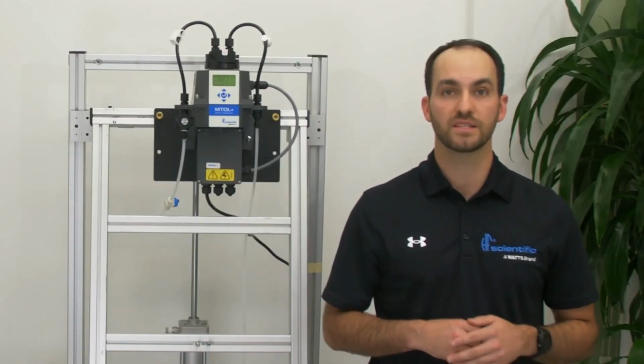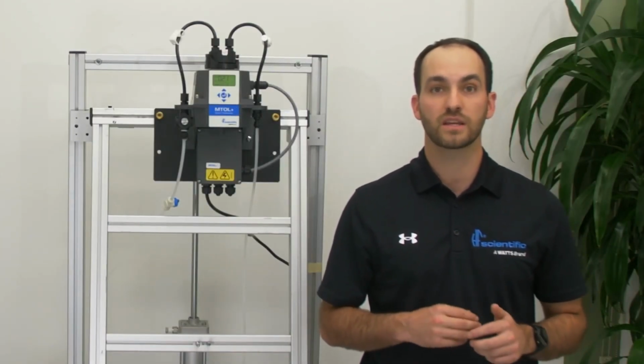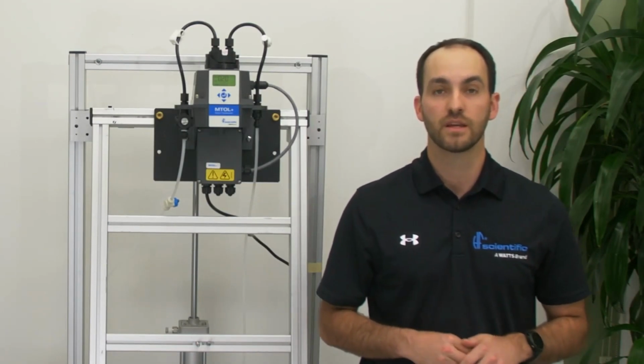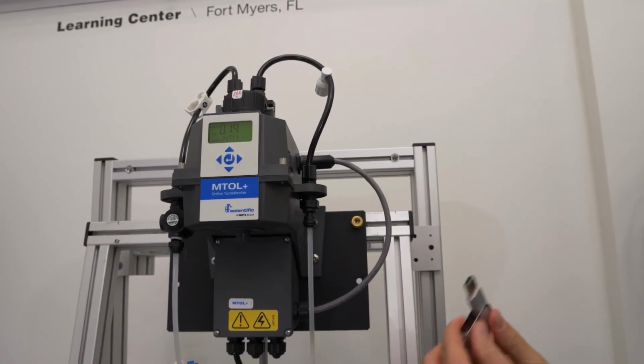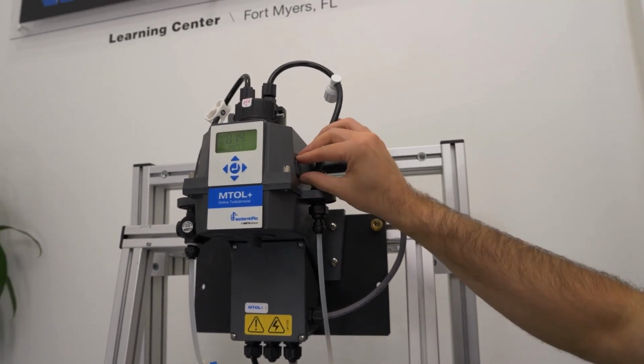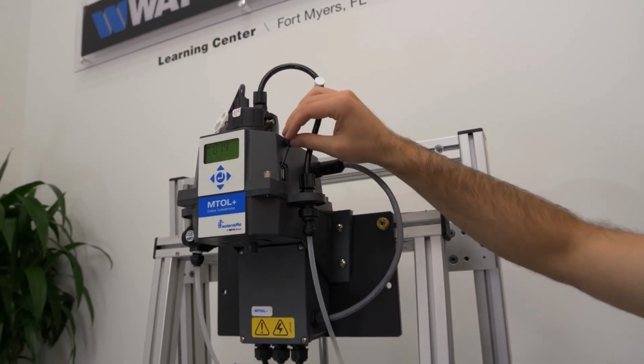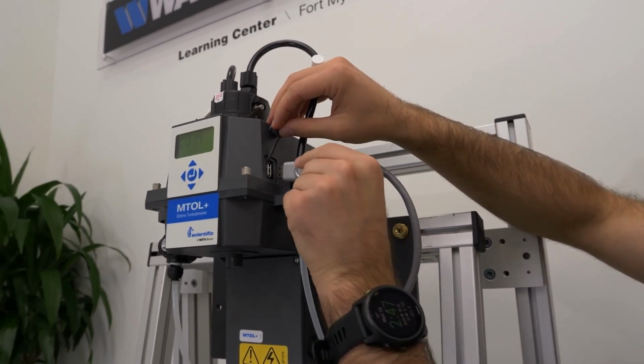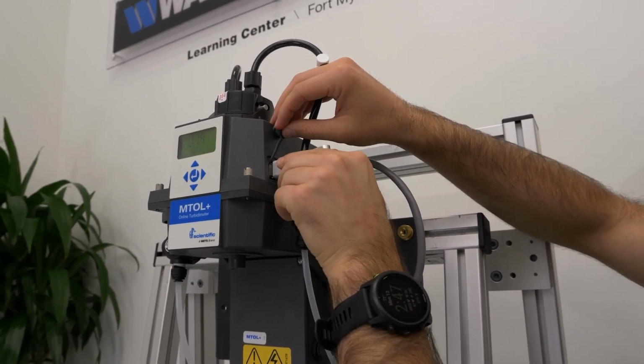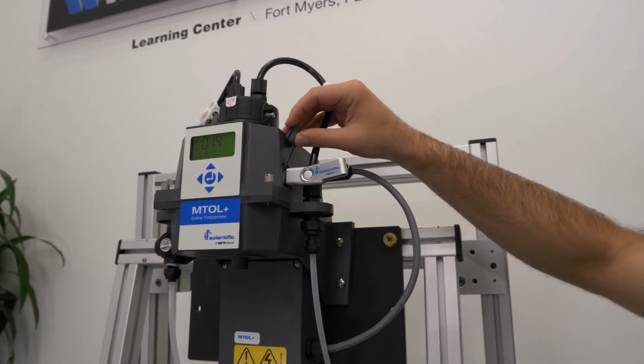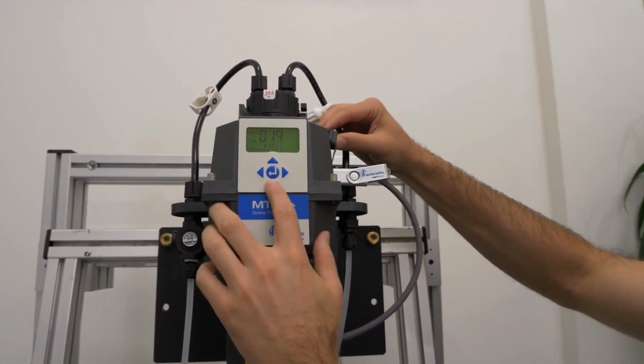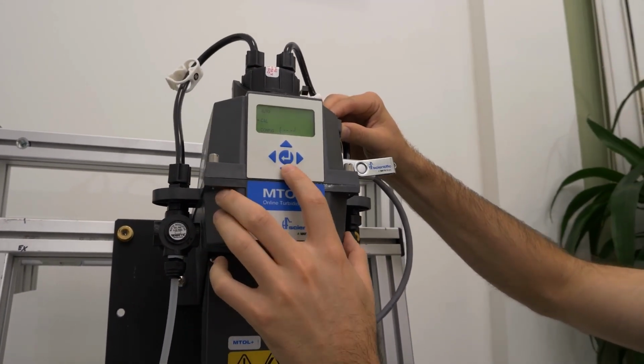Once you have plumbed and set up the analyzer, you may change the calibration range if desired. Calibration ranges offered are 0 to 10 NTU, 0 to 100 NTU, and 0 to 1000 NTU. You want to ensure you have a calibration kit for the correct analyzer range before changing the range. Use the down arrow to scroll to configuration mode and hit enter.